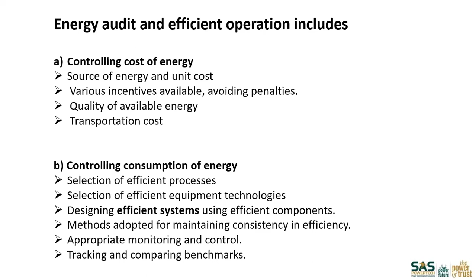A small electrical example I can give you here: there was a huge large software company, still existing in Pune, with around 1200 kilowatt load for an IT company, and they had huge large UPS systems working with them. The leaflet of those UPS systems, if you see, the overall efficiency mentioned was about 90 to 93%, but the manufacturer had not mentioned how much efficiency they would give if operated at 50% load. Unfortunately, when we measured, the efficiency at 50% load was hardly 53%. We could suggest something to them which they immediately implemented because they were cash rich, and they started saving about 5 lakh rupees per month on electrical energy just by going in for new energy efficient modular kind of UPS systems. So that kind of change is possible at times if a bigger mistake takes place.